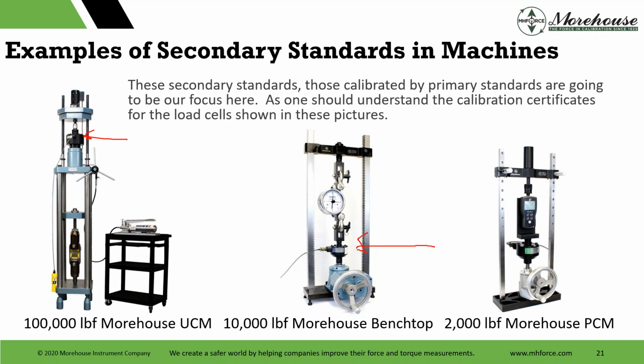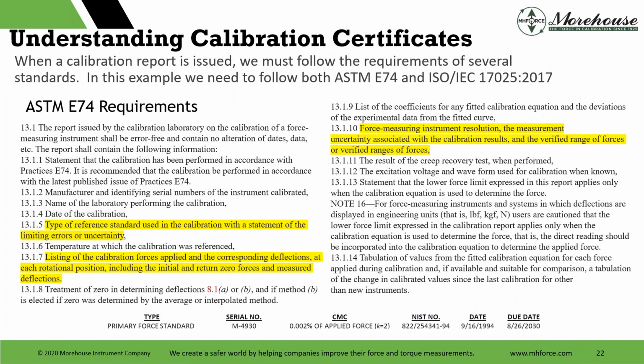So really what you want to know, the easiest thing you can say is, if we draw something, the lower the uncertainty of the reference standard, the more room we have, or people say, elbow room, the more room we have to be in tolerance. If we're using dead weight, we might have that much room. If we switch to secondary standards here, we might only have half the room to call an instrument in tolerance or make a statement of conformity or compliance. So that's covered in another webinar. You can go look at the one on risk. We cover it on that one as well.